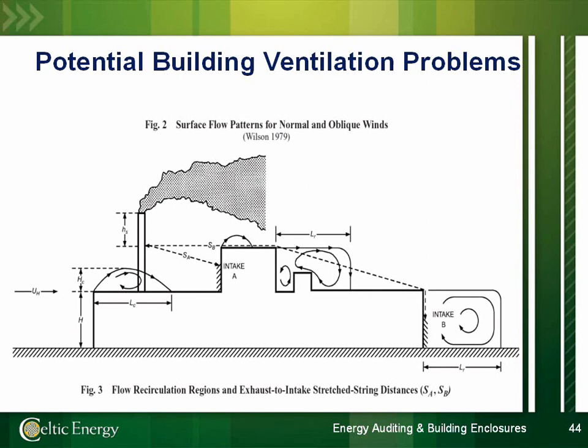And this is Chris again. I've seen this on several occasions where we're on a roof of a building somewhere, and the outside air intake will be no more than 10 feet, say, from an exhaust. And sometimes it's a toilet exhaust, sometimes it's a kitchen exhaust, and it causes terrible complaints and problems from the building occupants because they're smelling these things that should be taken away in the airflow, but it just doesn't happen because of the way it was designed.